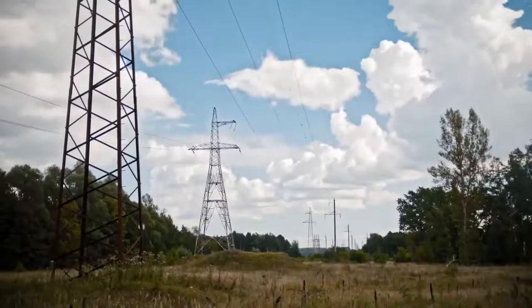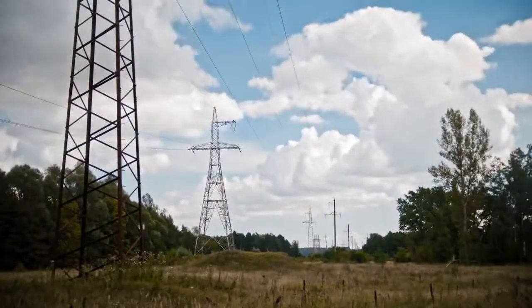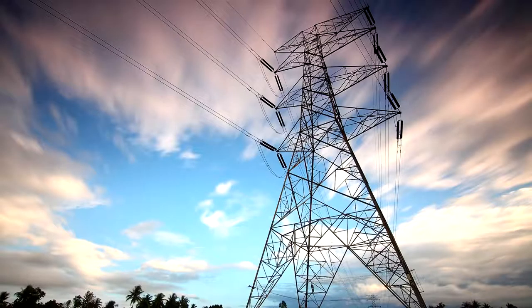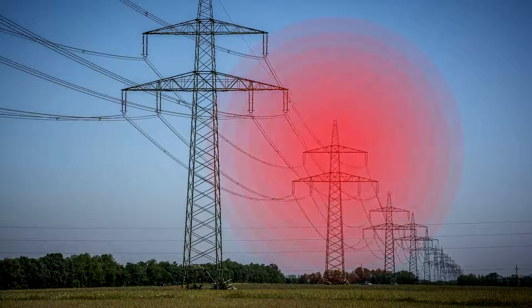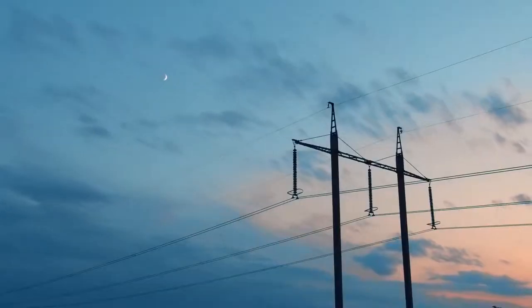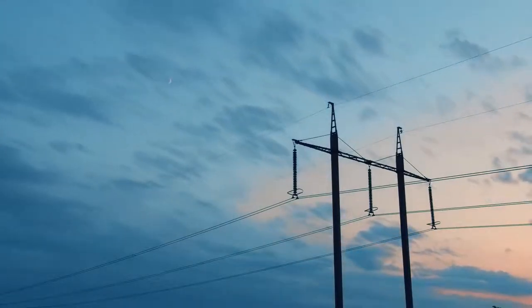Wind can also affect the conductors, causing oscillations that lead to damage or failure of the material. You'll often see these small devices called stockbridge dampers to absorb some of that wind energy. High voltage transmission lines also generate magnetic fields that can induce currents in parallel conductors like fences and interfere with magnetic devices, so the height of the tower is sometimes set to minimize EMF at the edge of the right-of-way. In certain cases, engineers even need to consider the audible noise of the transmission lines to avoid disturbing nearby residents.